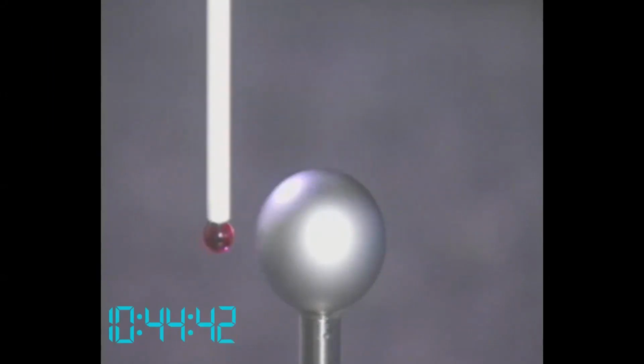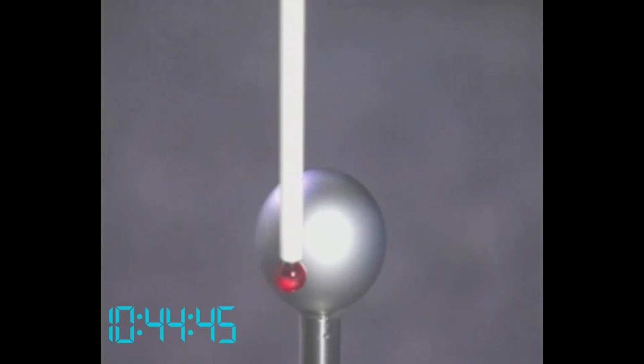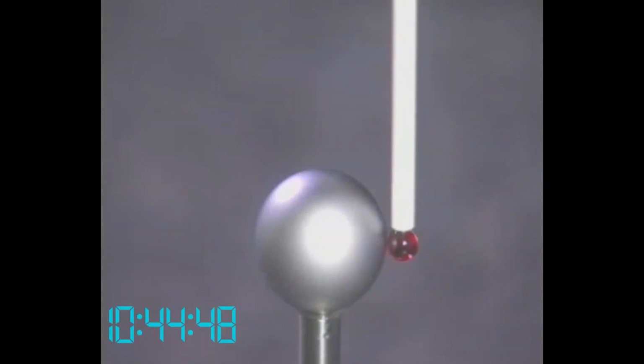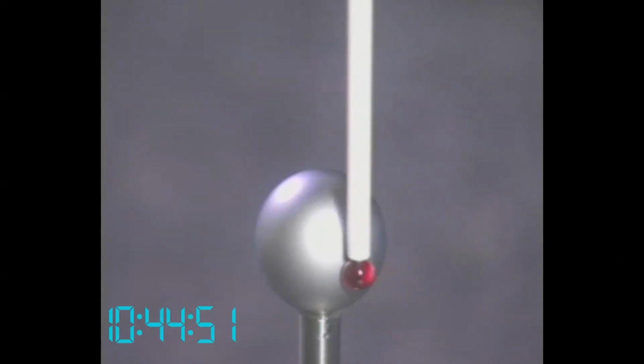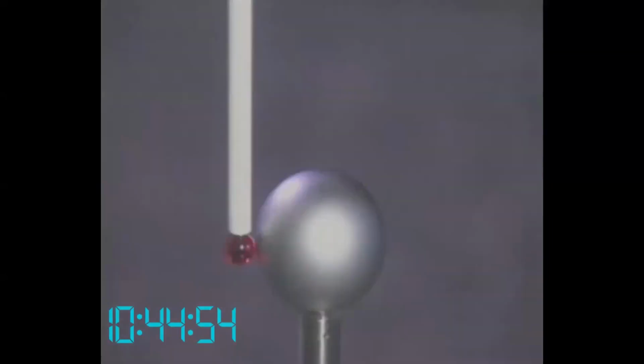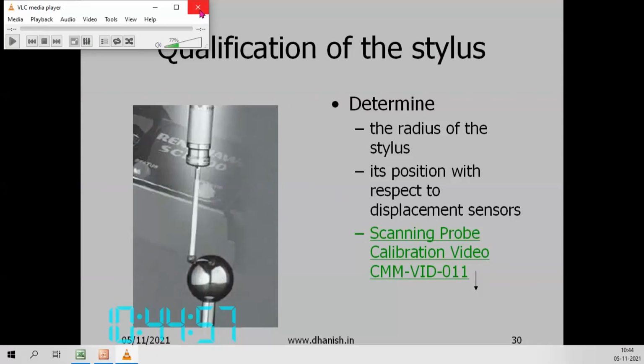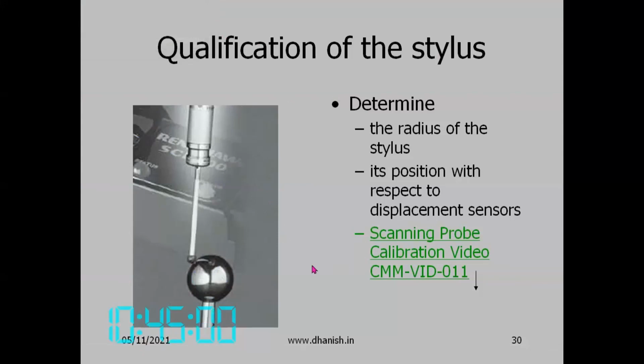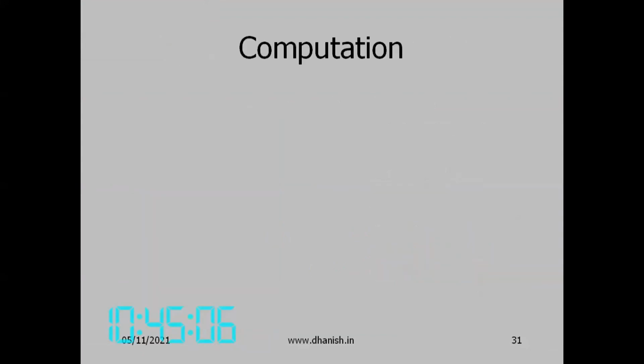We contact 4 points to get the approximate center. It's a continuous scanning probe. It continuously captures the data. So that is stylus qualification. After that, the CMM measures the coordinates, and based on the stylus position, it compensates for the direction of contact and gives the surface coordinates. That is one part.